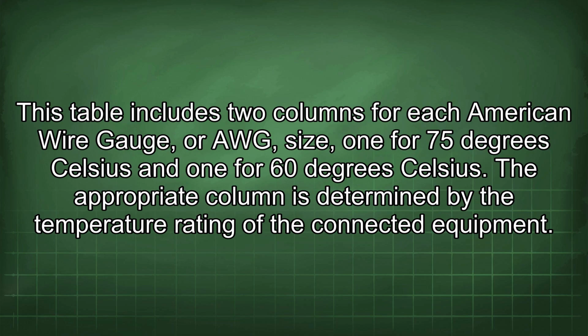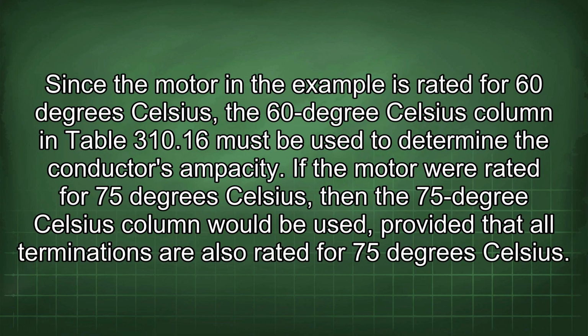This table includes 2 columns for each American wire gauge, or AWG, size, one for 75 degrees Celsius and one for 60 degrees Celsius. The appropriate column is determined by the temperature rating of the connected equipment. Since the motor in the example is rated for 60 degrees Celsius, the 60 degrees Celsius column in Table 310.16 must be used to determine the conductor's ampacity.